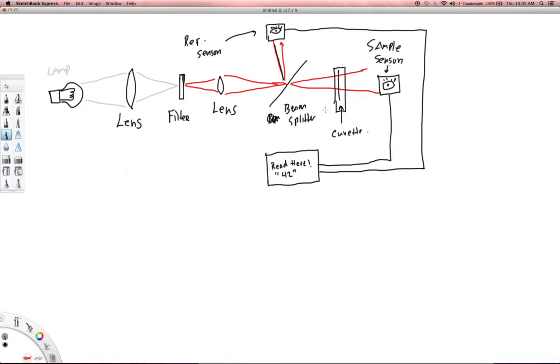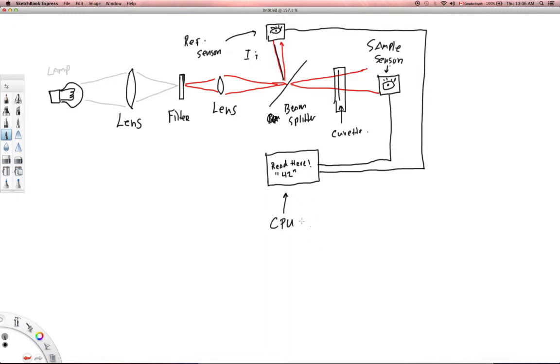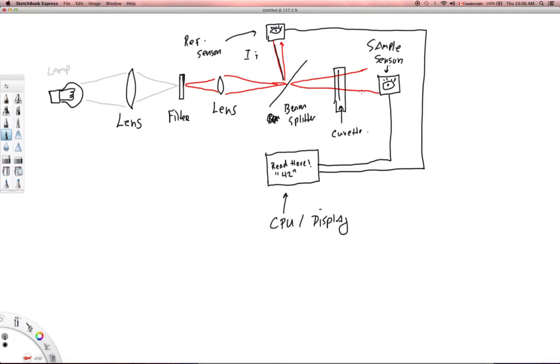And then the information from the reference sensor, so this is the I1 here, this is intensity coming in. This is going to tell the, and this is a little microprocessor here, so this is my central processing unit, and then my display, where I actually get my information. So this is going to tell me, okay, boom, this is the intensity of the light coming in, that goes to the CPU. And then the sample sensor is going to say, hey, this is the intensity of the light coming out, so this is my I2 here. That information goes into the CPU.